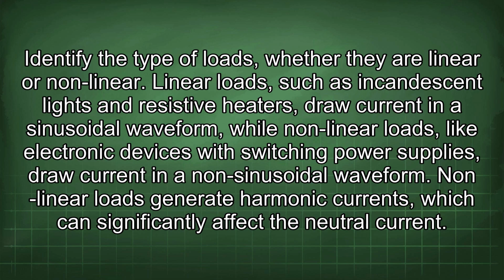Identify the type of loads, whether they are linear or non-linear. Linear loads, such as incandescent lights and resistive heaters, draw current in a sinusoidal waveform, while nonlinear loads, like electronic devices with switching power supplies, draw current in a non-sinusoidal waveform. Nonlinear loads generate harmonic currents, which can significantly affect the neutral current.